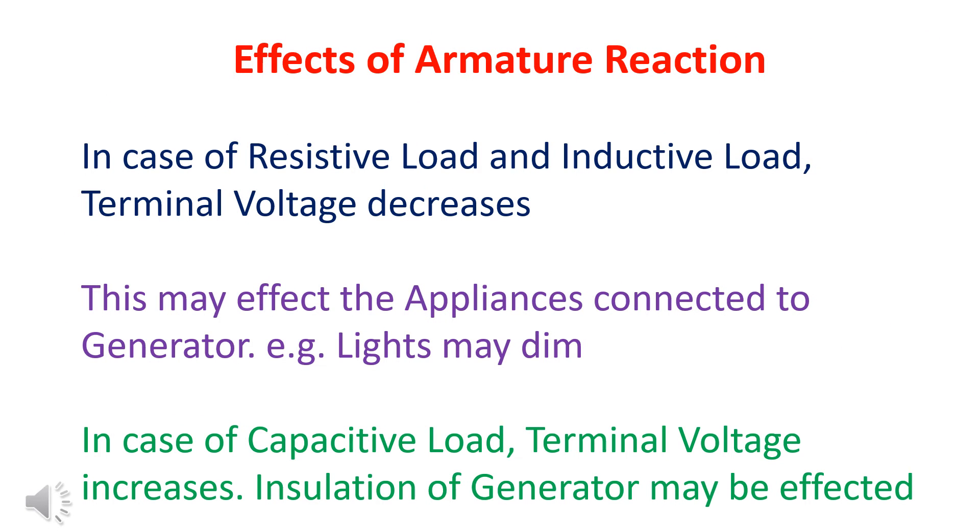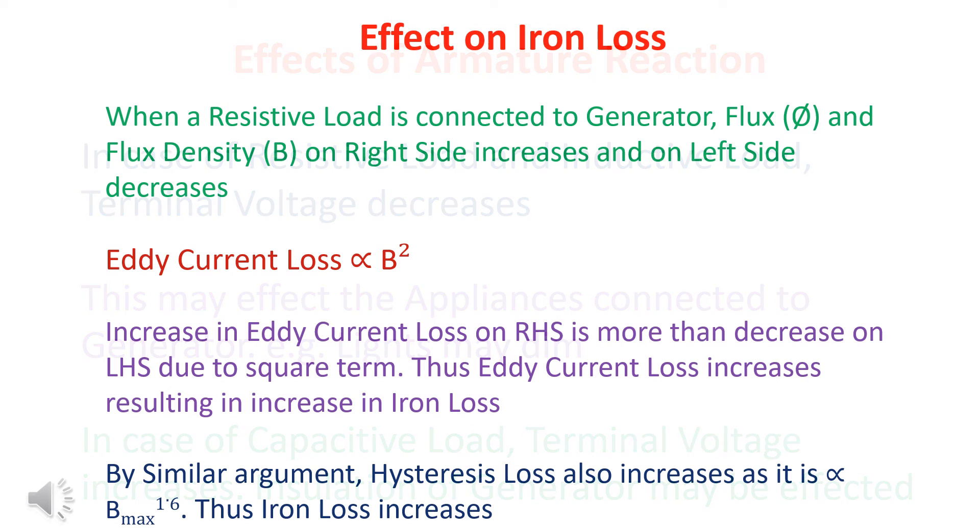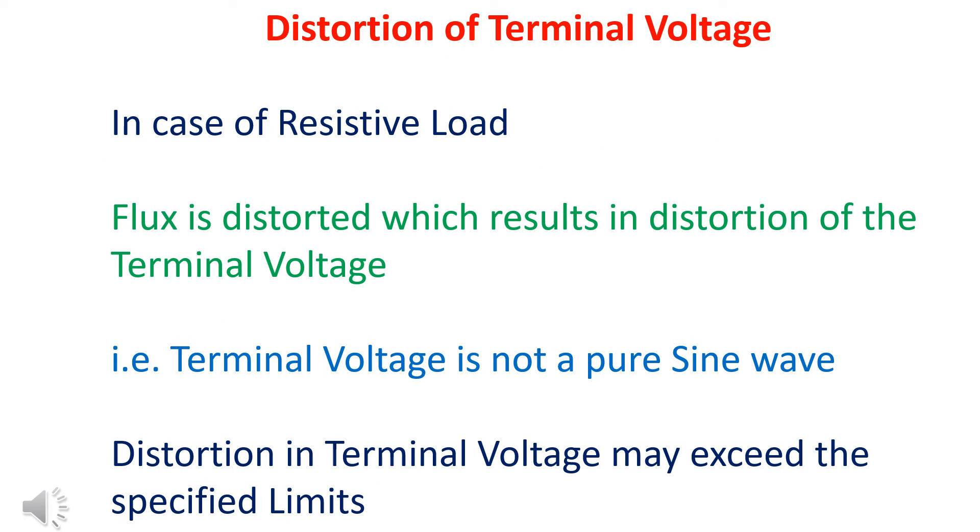There are various effects of armature reaction. In case of resistive and inductive load, terminal voltage decreases. This may affect appliances. In case of capacitive load, voltage increases. This may affect insulation. Iron loss increases in case of resistive load. In case of resistive load, flux is distorted, resulting in distortion of terminal voltage.